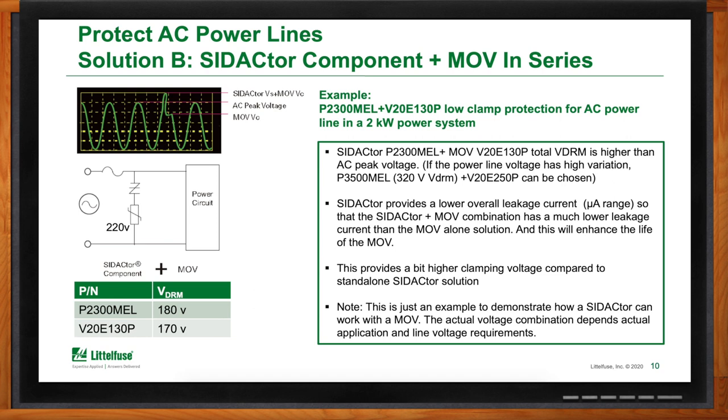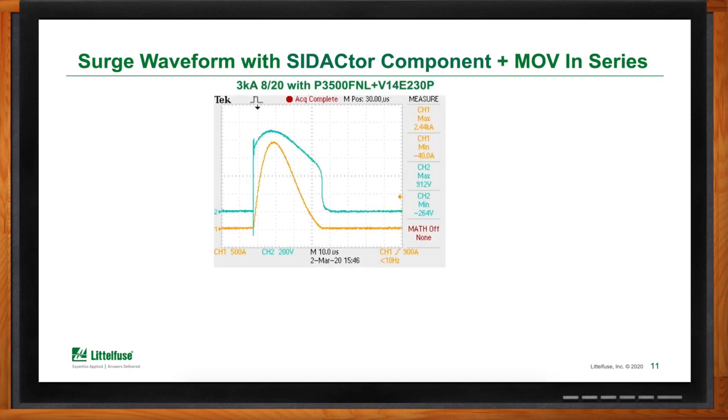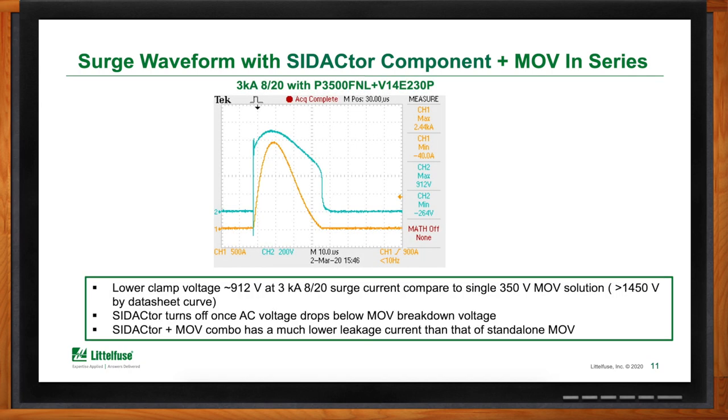Looking at the MOV plus SIDACtor solution on scope, comparing with a 350V MOV by itself, the combination yields a much lower clamp voltage. The SIDACtor will first turn on and then the MOV will clamp at a much lower voltage. Also, the SIDACtor and MOV combination yields a much lower leakage current than a standalone MOV.